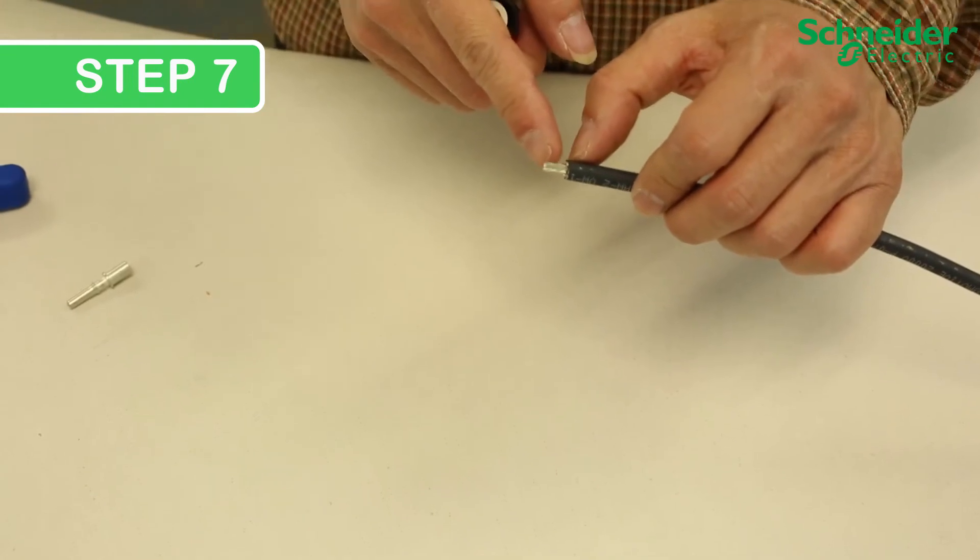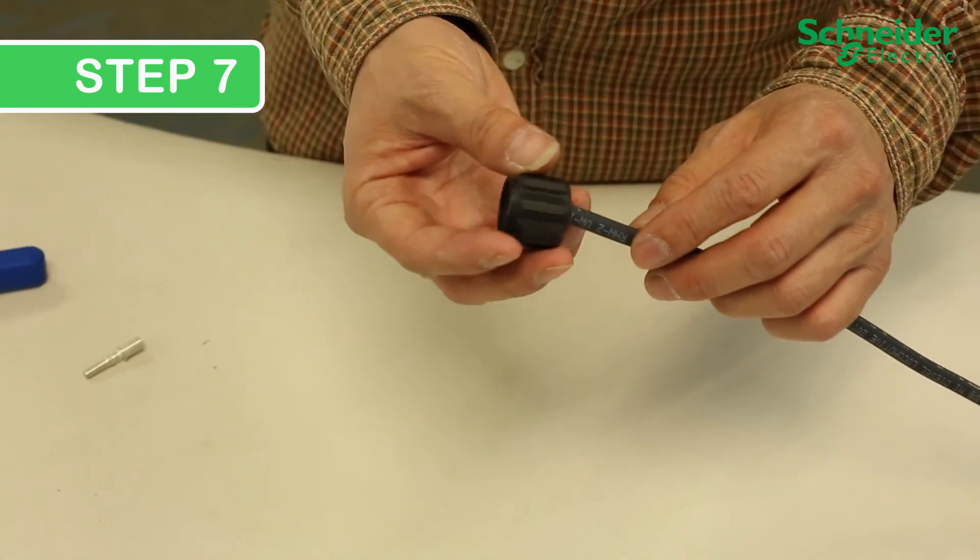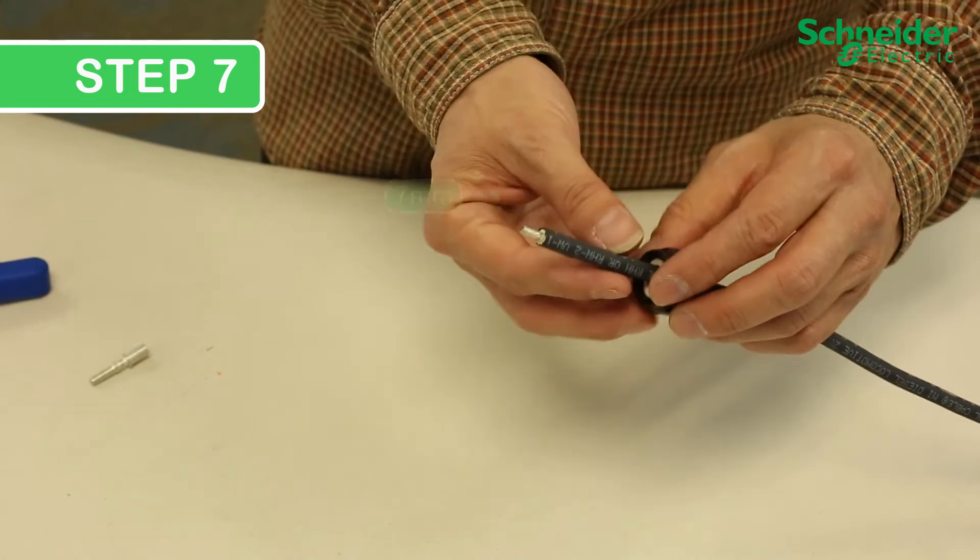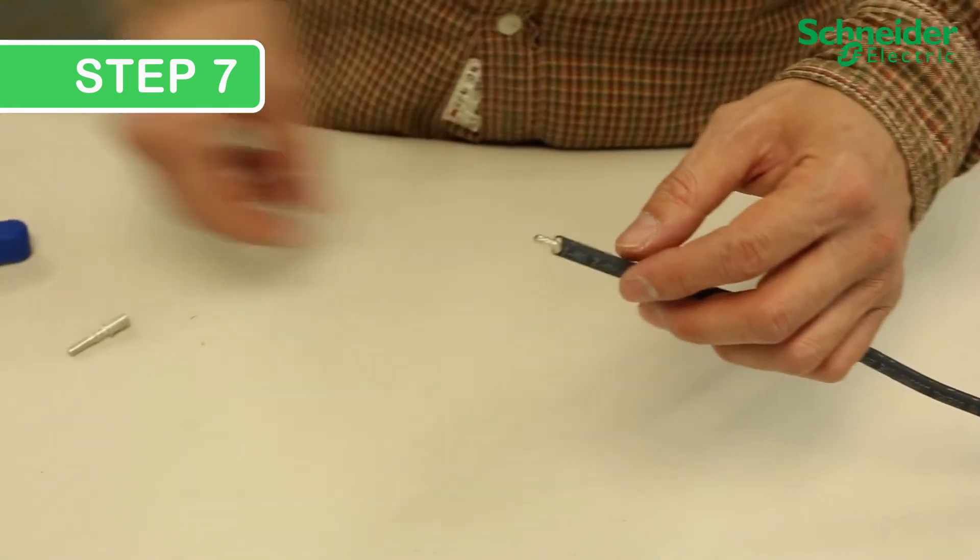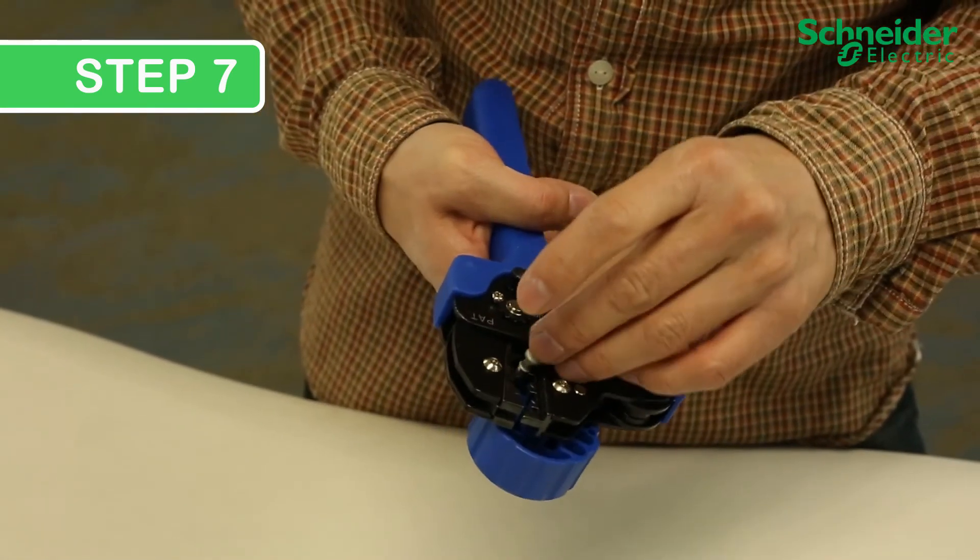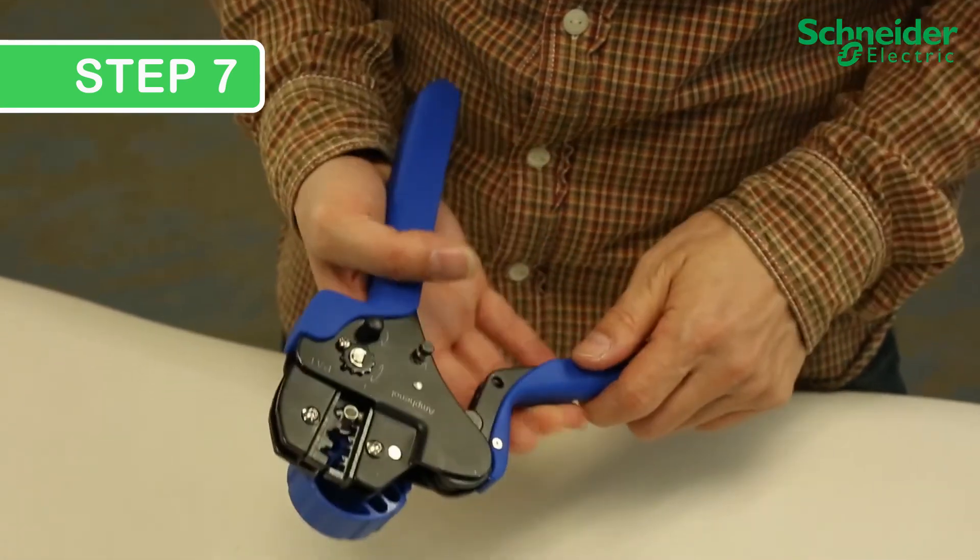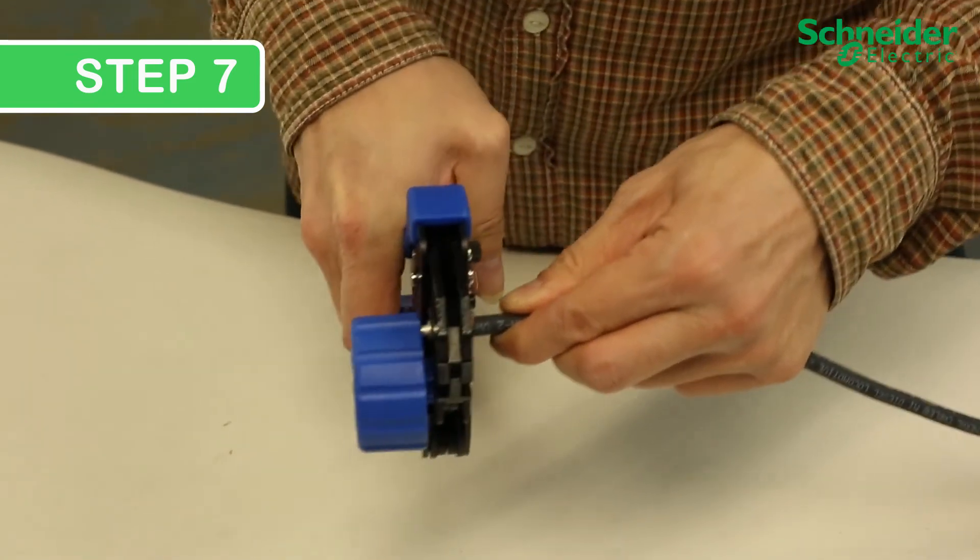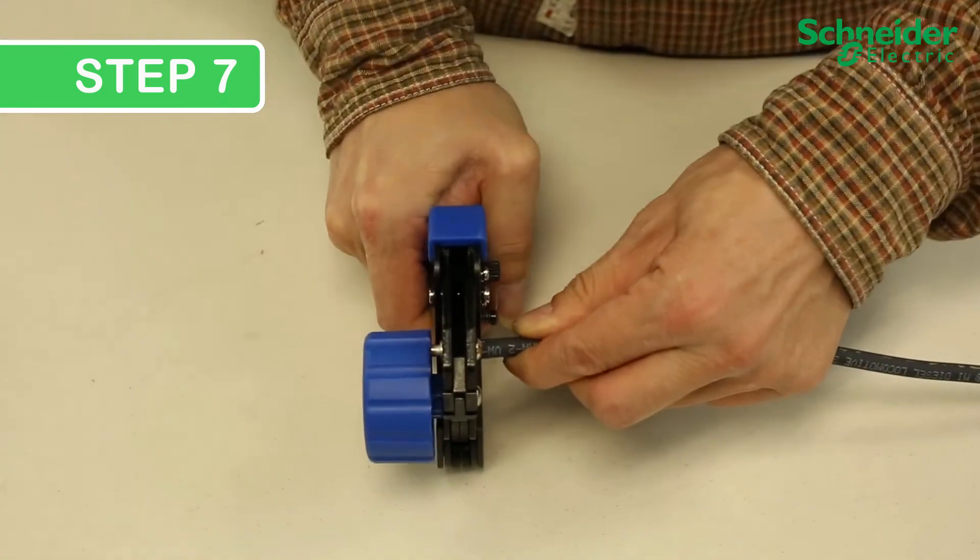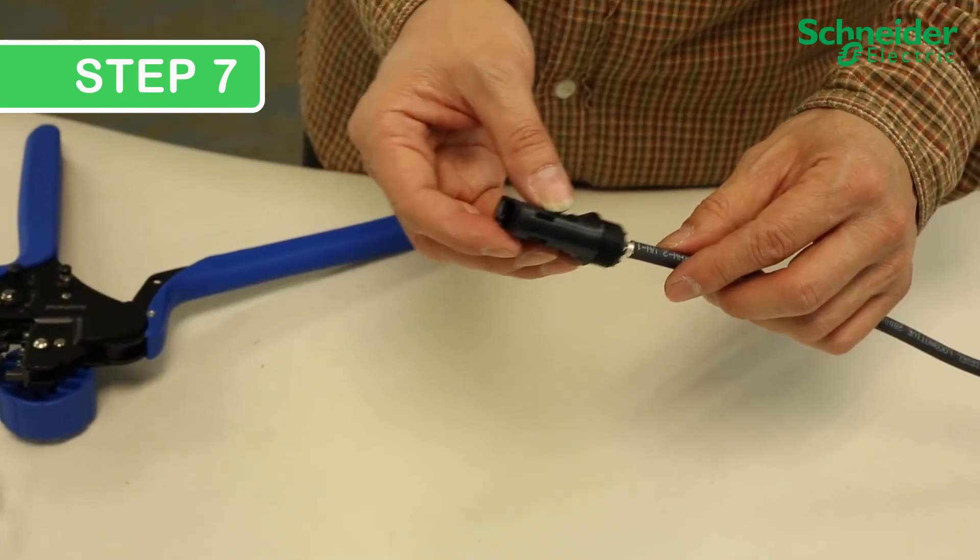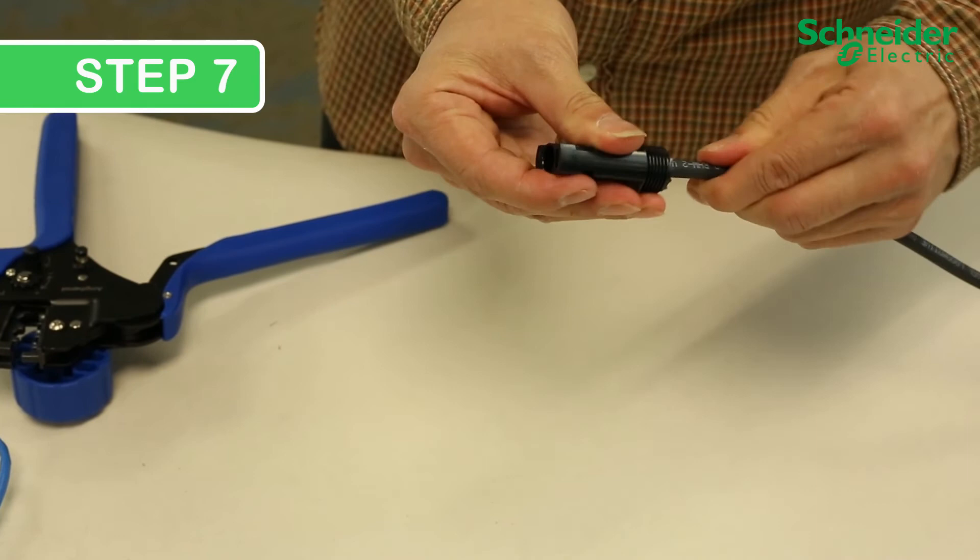Step 7: Installing PV connectors. Strip 7 millimeters of cable jacket. Feed that through tightening nut. Put the pin in the correct type of crimper, Amphenol for H4 and Multi-Contact for MC4. Once crimped, install your insulator cap and tighten the connector using the manufacturer-recommended tools for the PV connector.